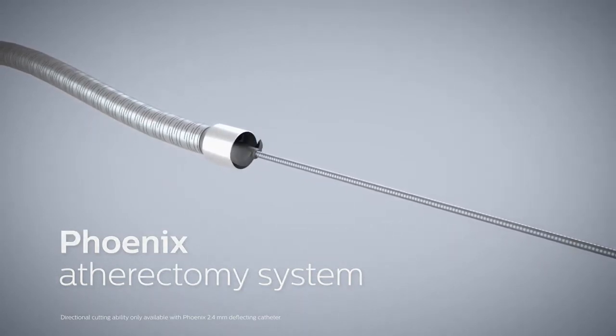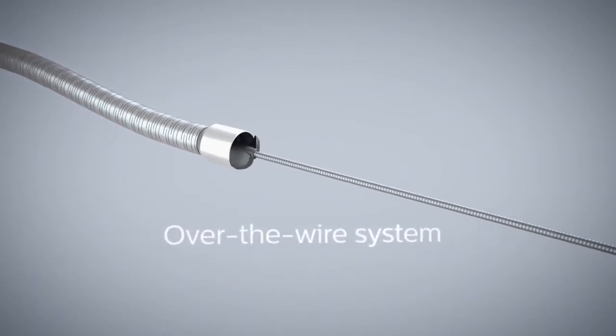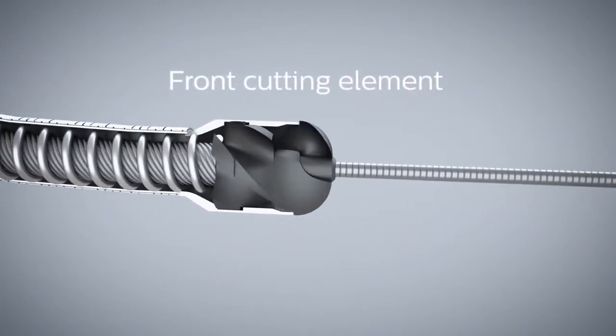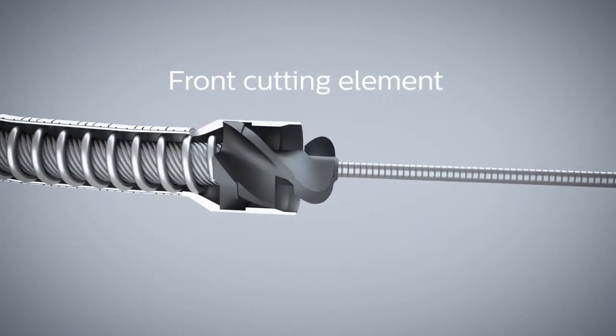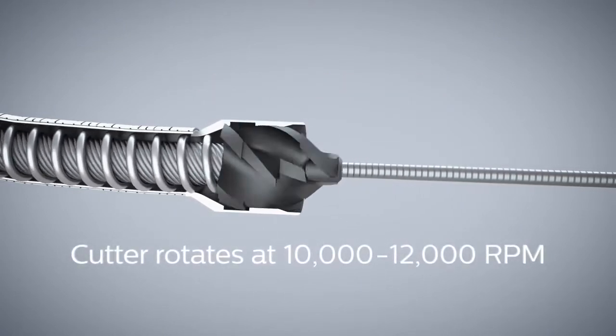The Phoenix atherectomy system is an over-the-wire peripheral atherectomy catheter. It has a front cutting element located at the distal tip which rotates at 10,000 to 12,000 rpm.